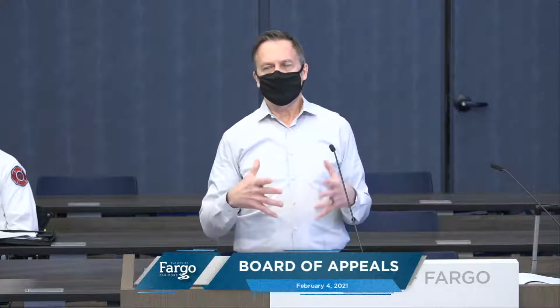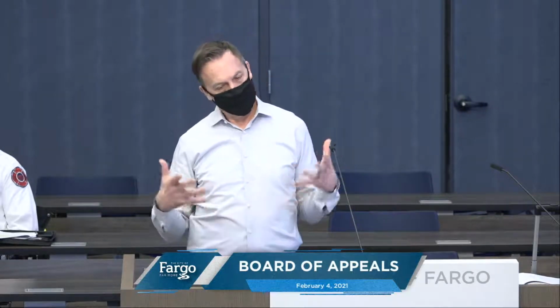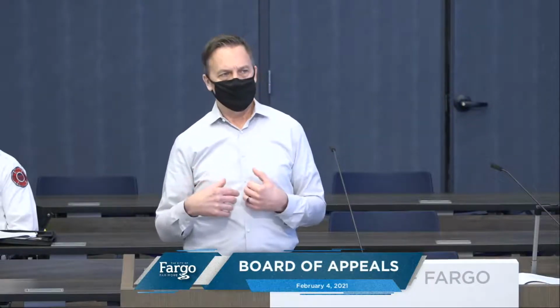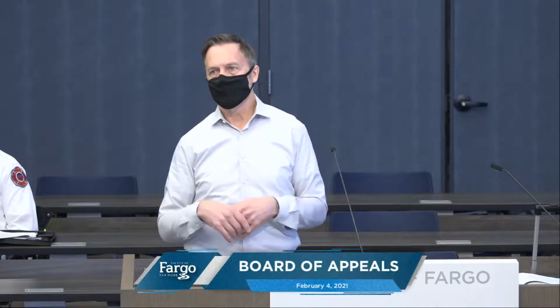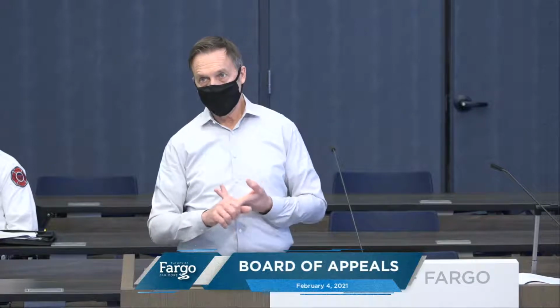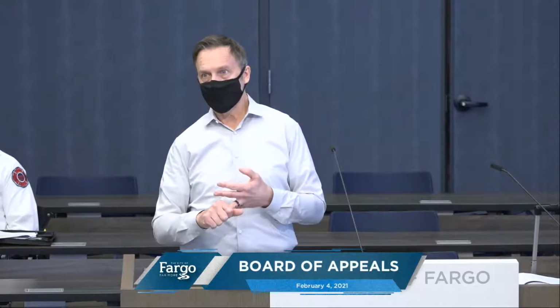So it's where do you start and stop that wall you're talking about? I mean, the appellant even brought it up. Well, we'll do it out to the edge. No, that's not enough. In our world, fire barriers don't stop. They have to get somewhere. They have to get to another fire wall, fire barrier, fire rated something.